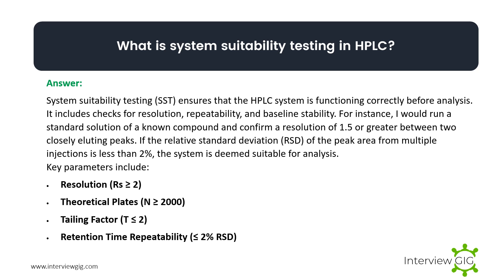What is system suitability testing in HPLC? System suitability testing ensures that the HPLC system is functioning correctly before analysis. It includes checks for resolution, repeatability, and baseline stability. For instance, I would run a standard solution of a known compound and confirm a resolution of 1.5 or greater between two closely eluting peaks. If the relative standard deviation of peak area from multiple injections is less than 2%, the system is deemed suitable. Key parameters include resolution, theoretical plates, tailing factor, and retention time repeatability.